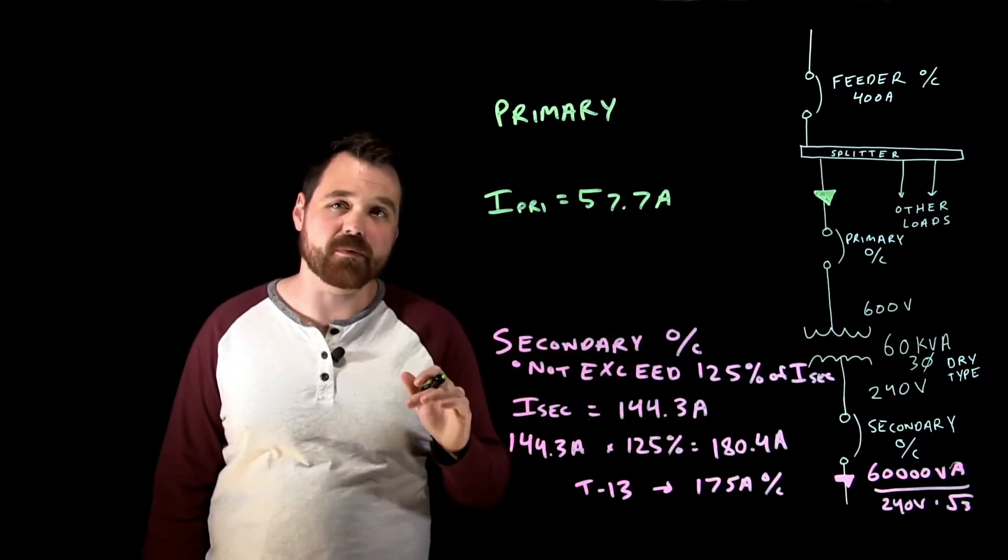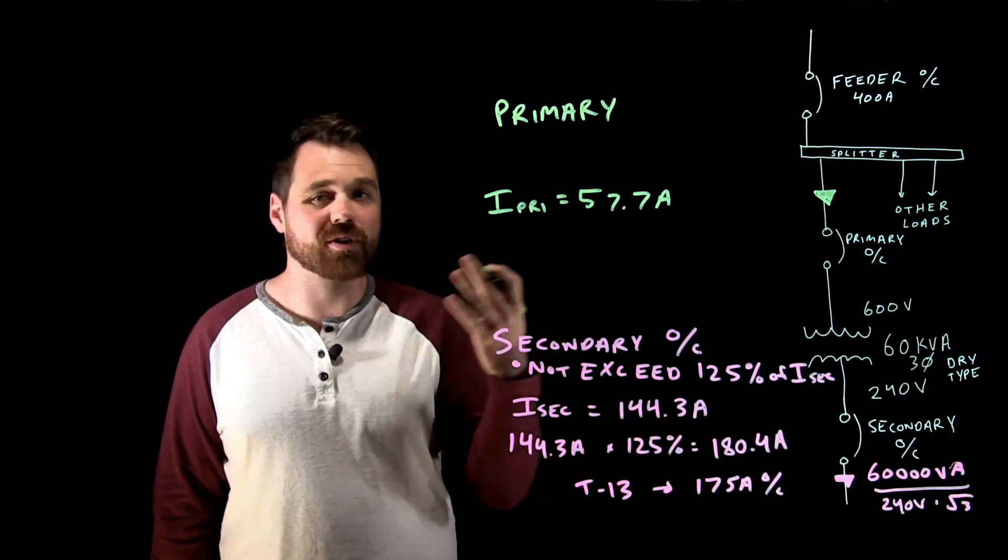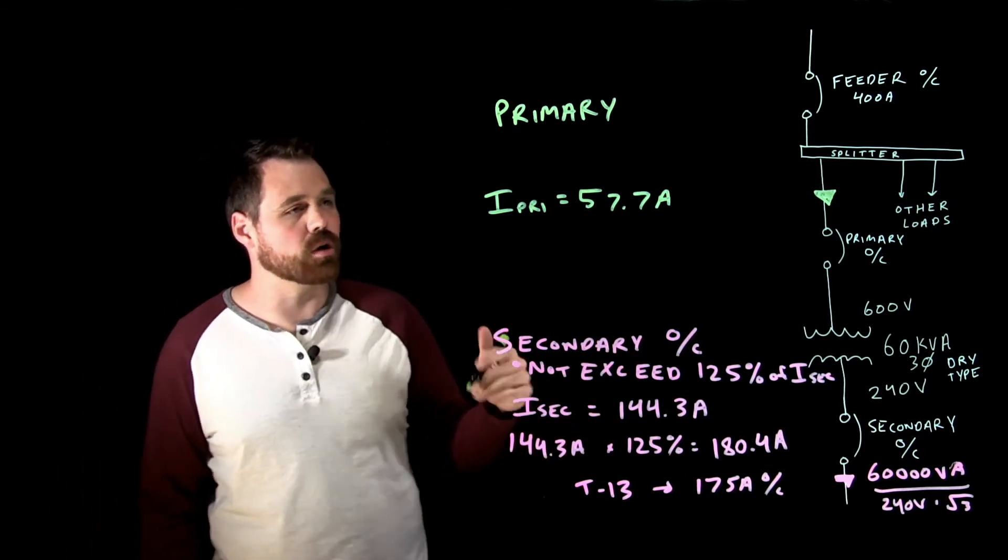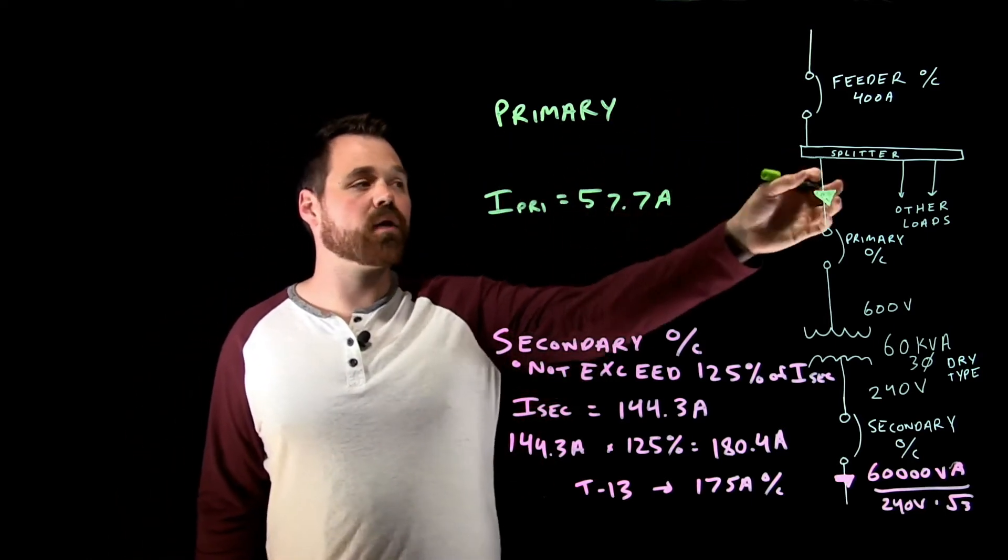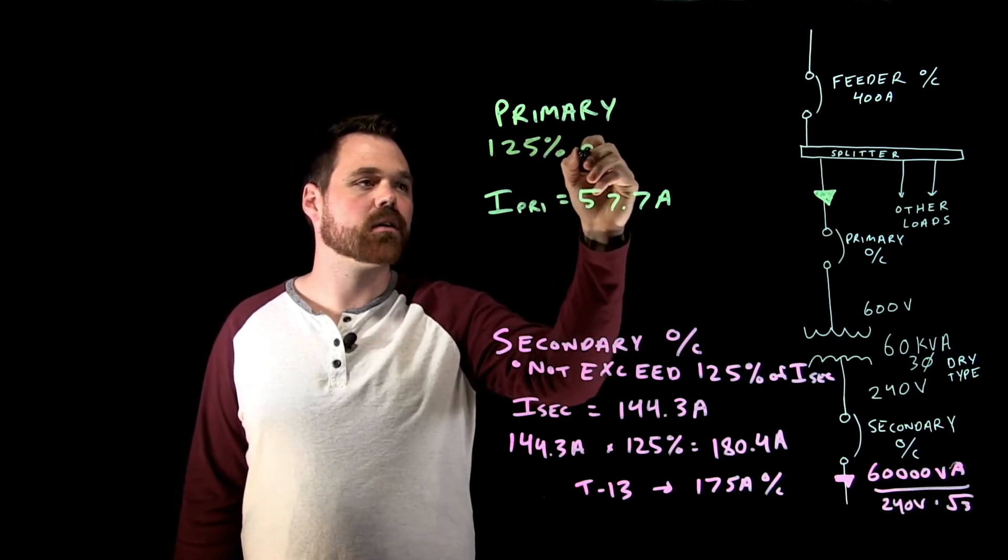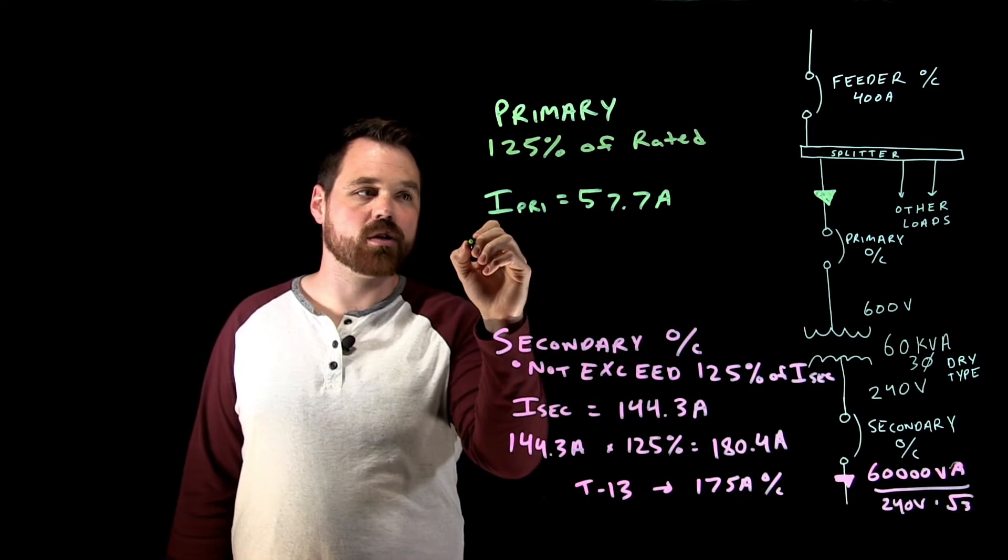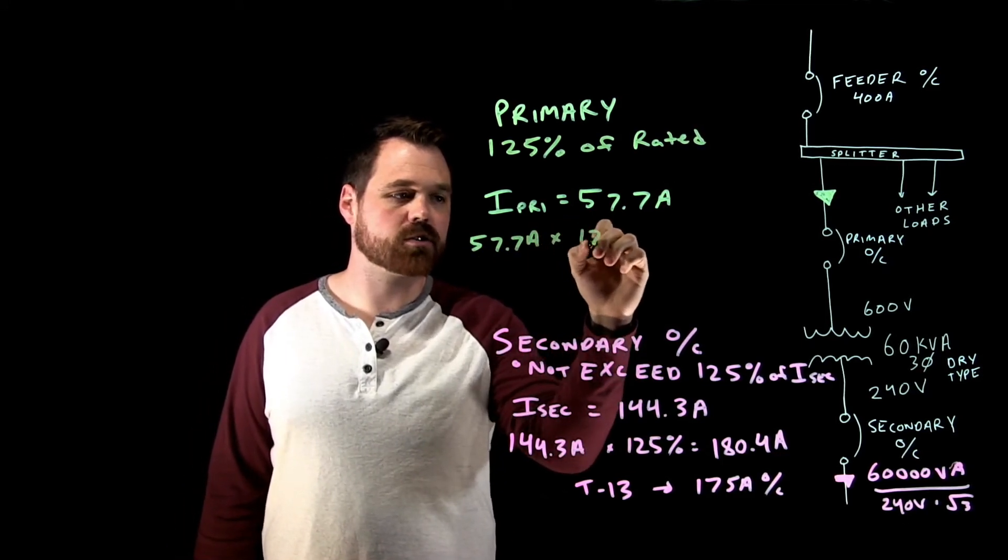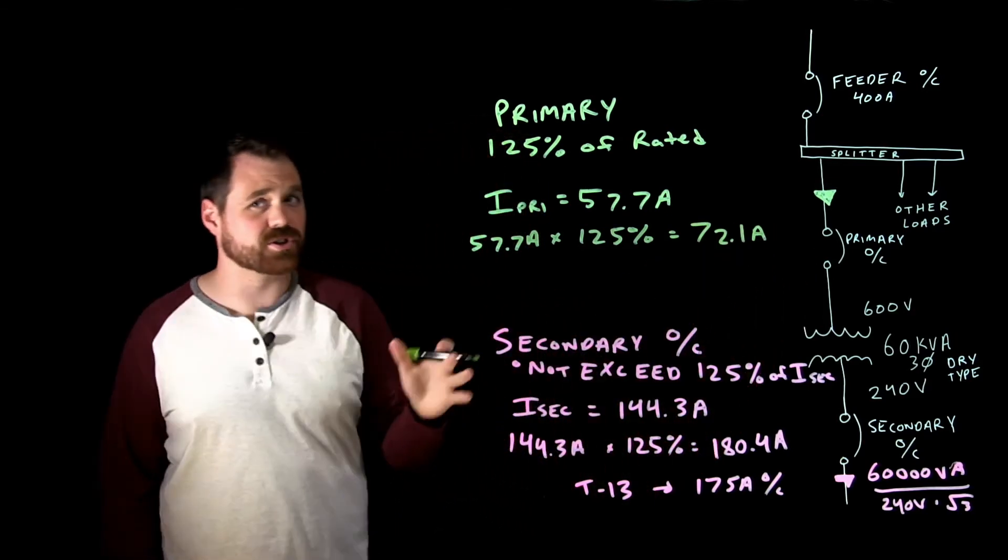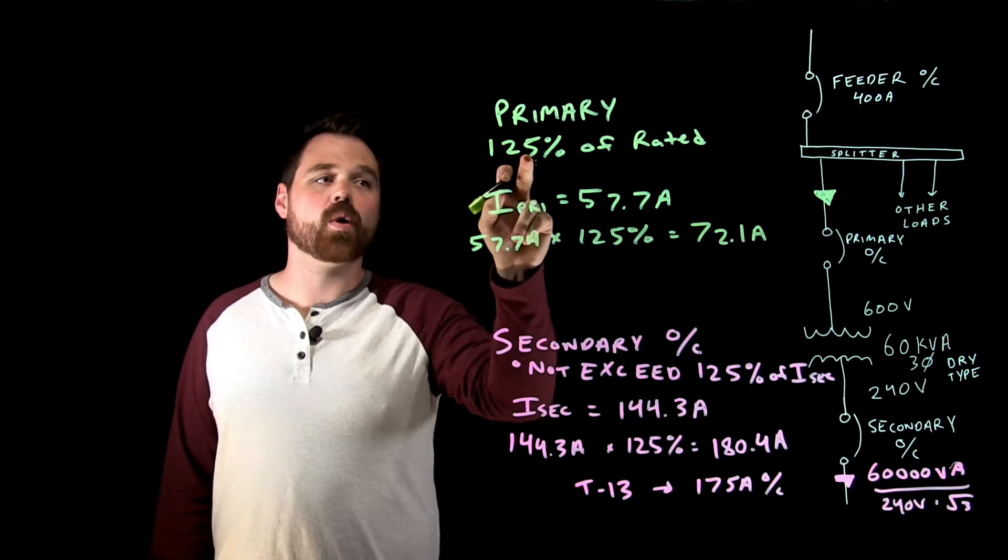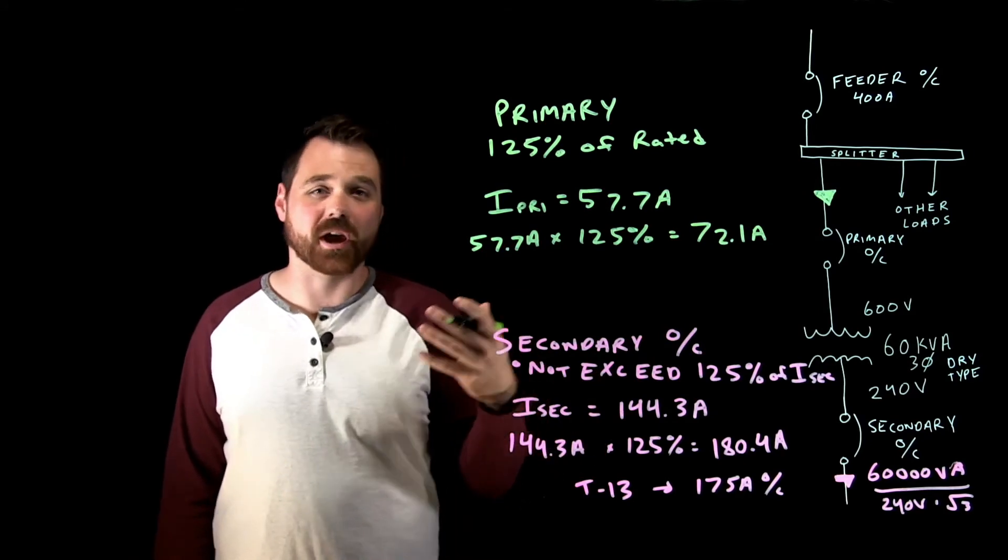We just determined we need one anyways. Also if I had no secondary overcurrent at all then I 100 percent will need that primary overcurrent and this is how we size it. I have my primary current 57.7 amps. This tells me my primary overcurrent device needs to be 125 percent of rated current. So in this case we are going to go 57.7 amps times 125 percent which gives us 72.1 amps.